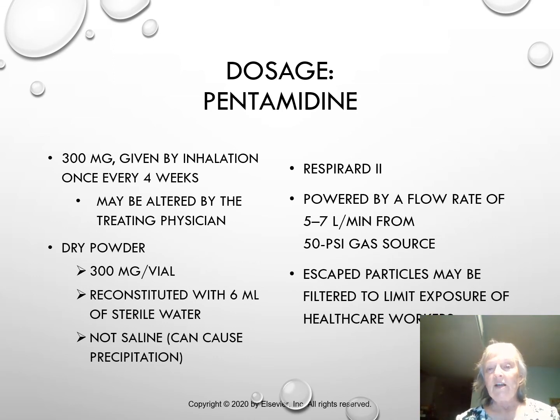Respirgard II is the device we use it with. It has to be powered by a flow rate of 5 to 7 liters per minute from a 50 psi gas source. You have to wear protection. You do not want to be exposed to this.